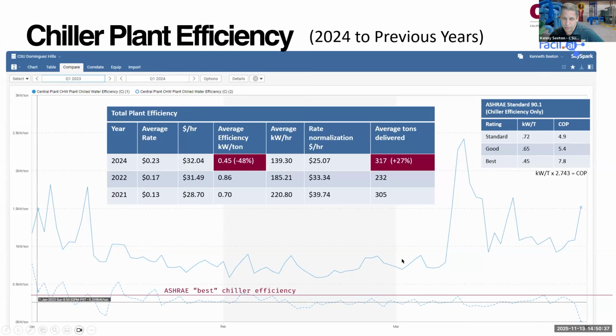You can see the graph of where we used to be on our efficiency. We used to run the plant like a lot of people, 5 degrees above wet bulb. What the AI is doing is adjusting our condensing water set point. Instead of it being just a static 5 degrees, 7 degrees, 75 degrees, it's dynamically adjusting it every 5 minutes. What we're finding is that it's not always better to burn more fan horsepower to save compressor horsepower, but there's a point where the two mix, and you've got to find the point of diminishing returns.